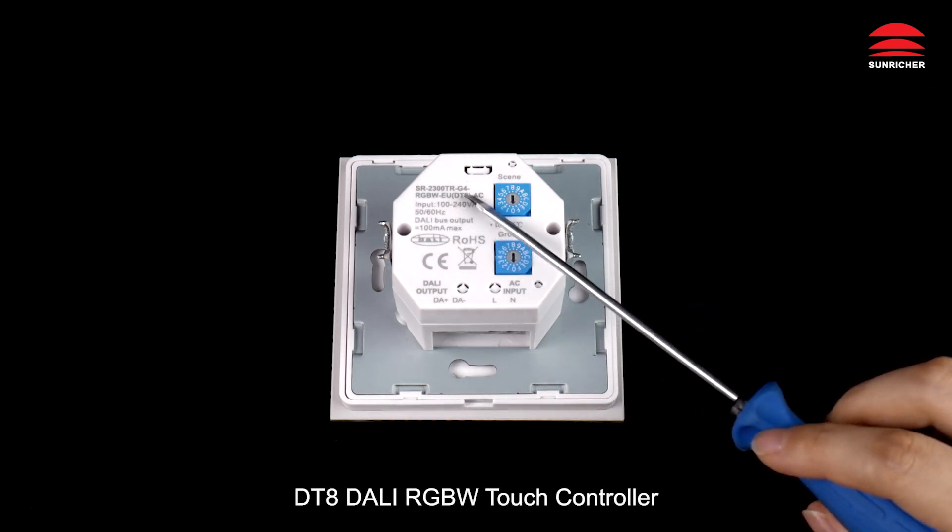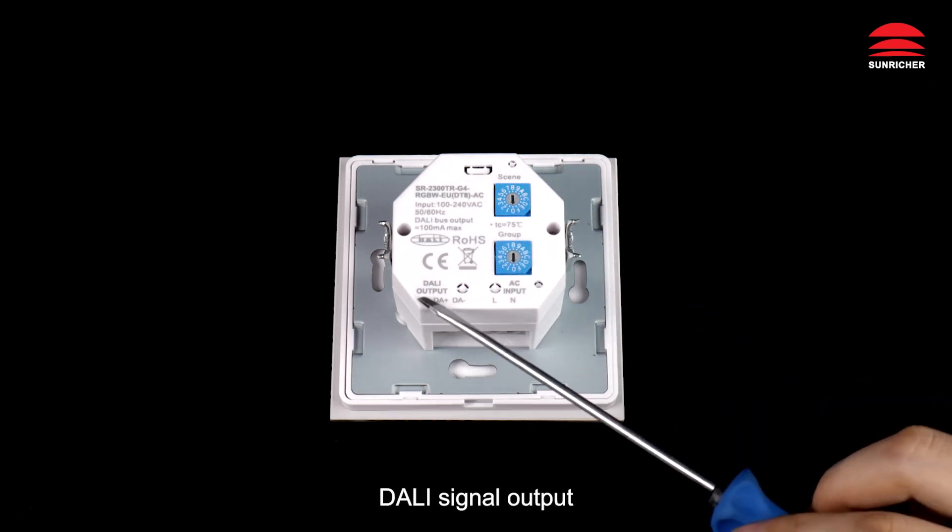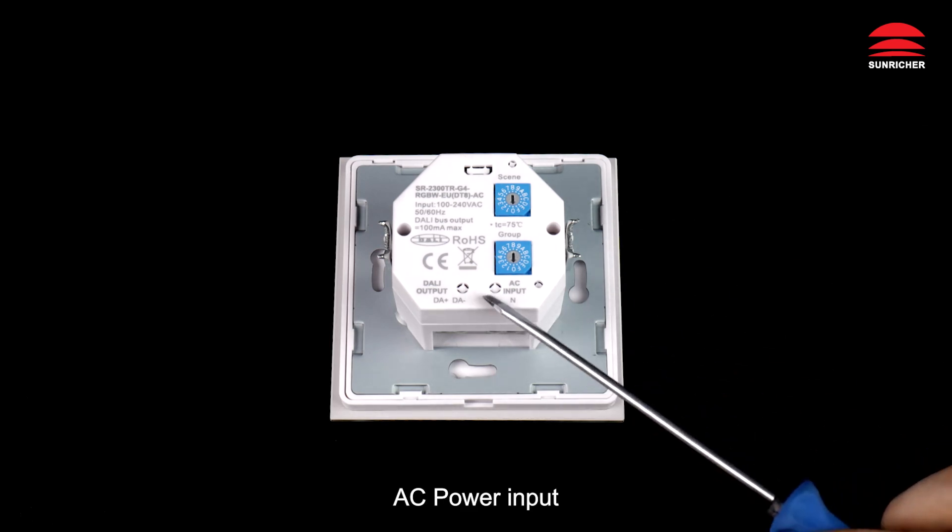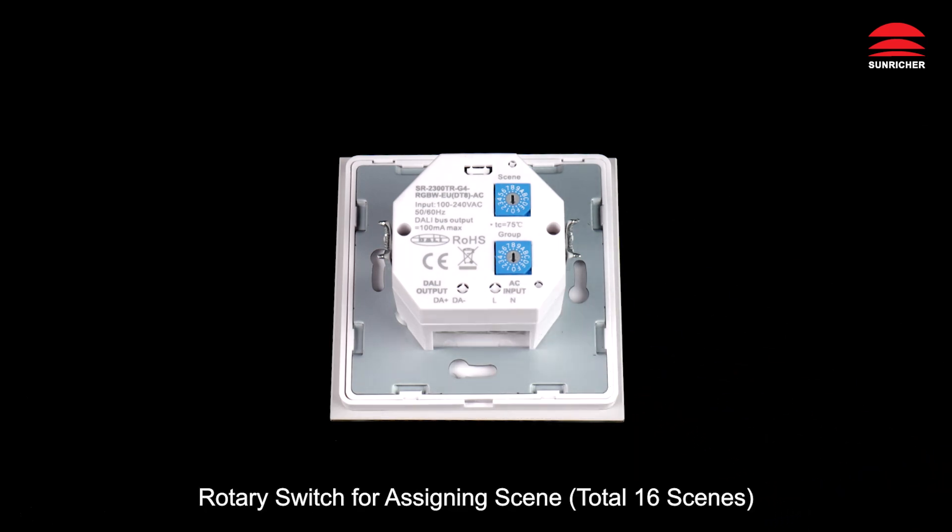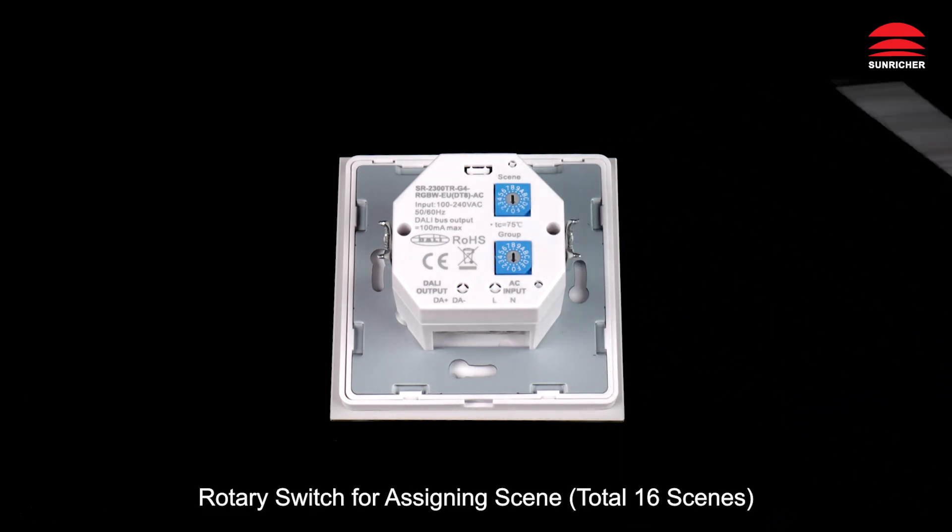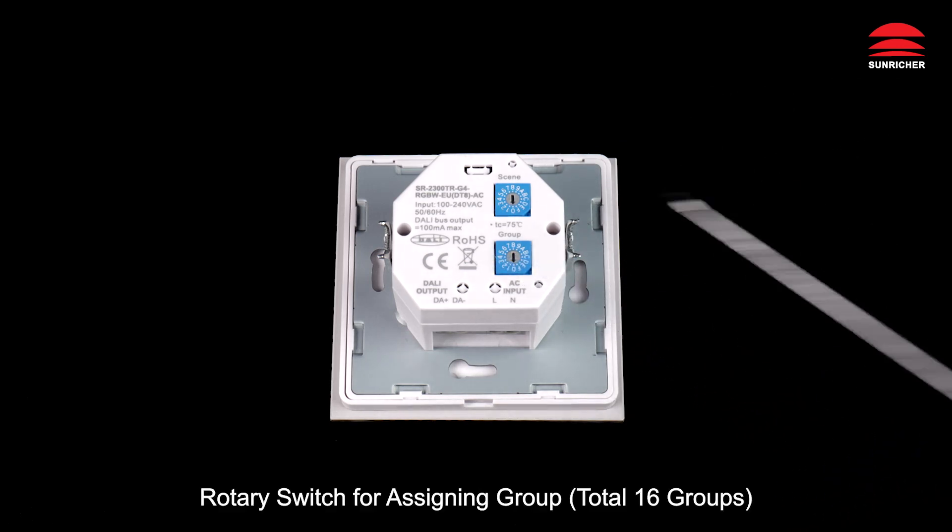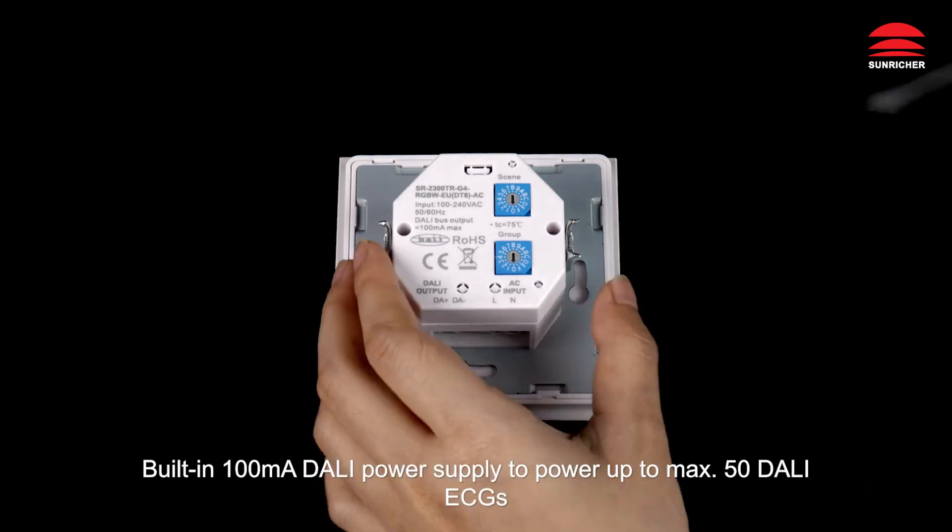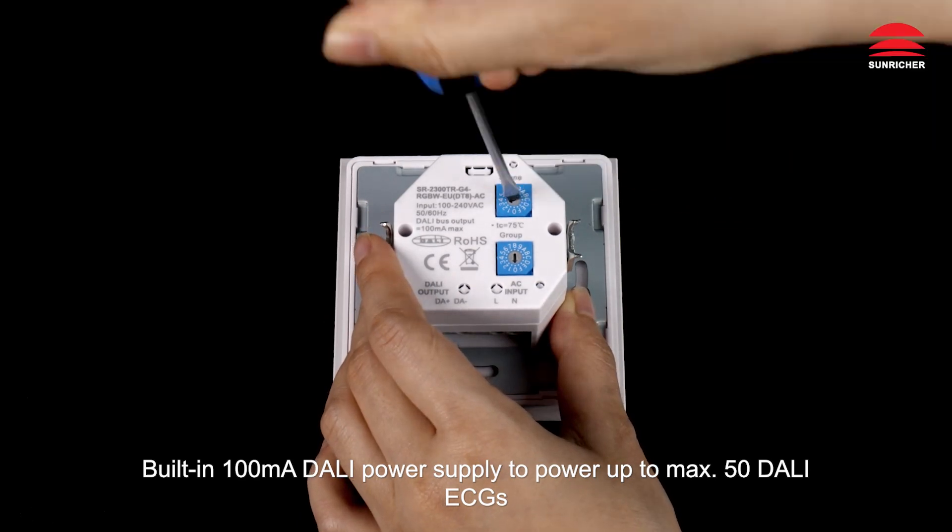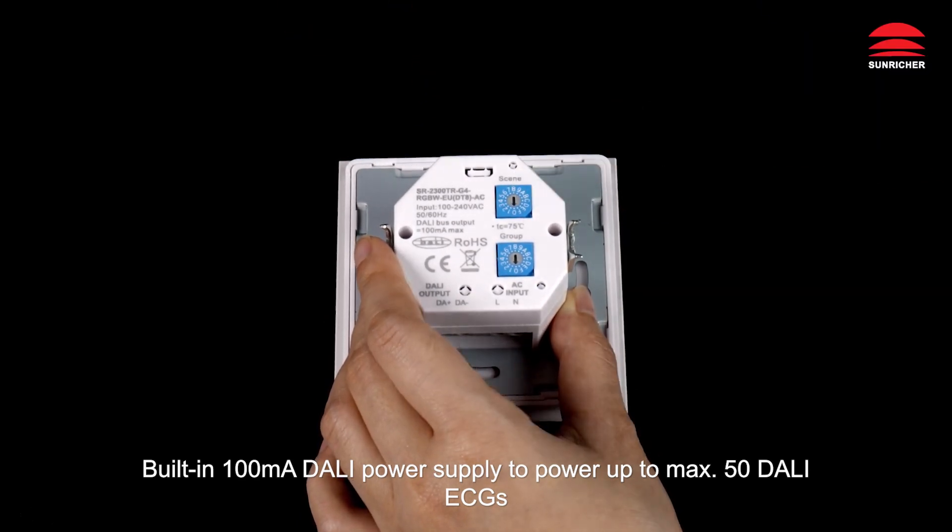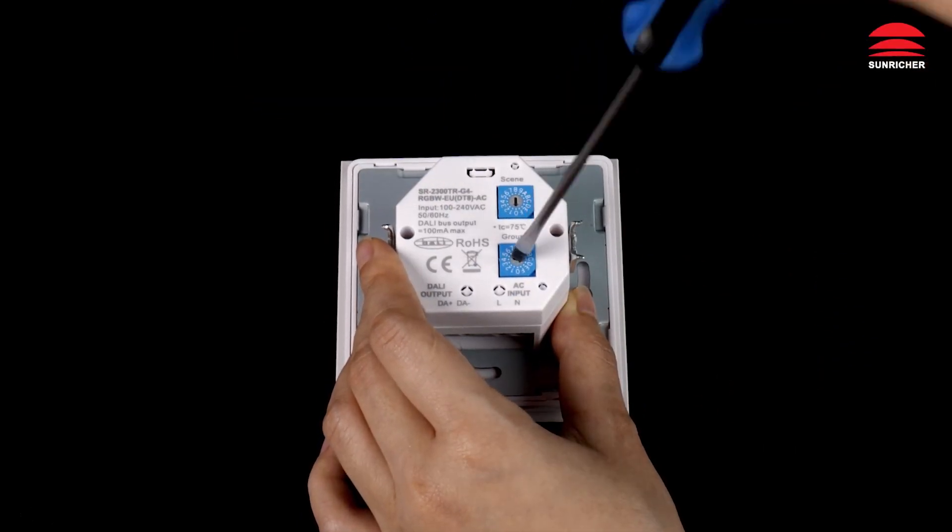DT8 DALI RGBW touch controller. DALI signal output, AC power input, rotary switch for assigning scene—total 16 scenes. Rotary switch for assigning group—total 16 groups. Built-in 100 milliampere DALI power supply to power up to max 50 DALI ECGs.